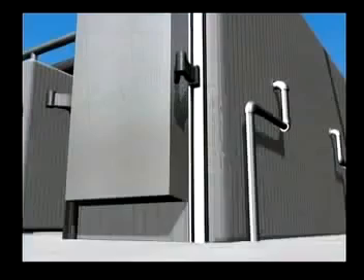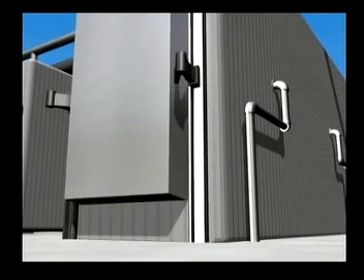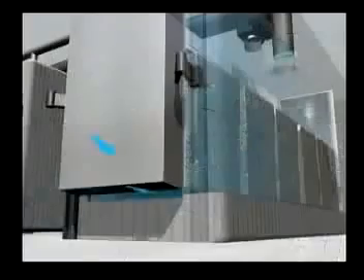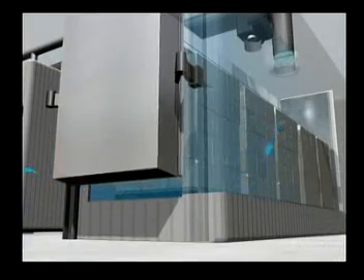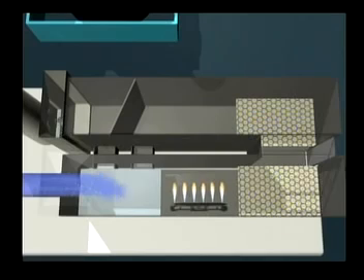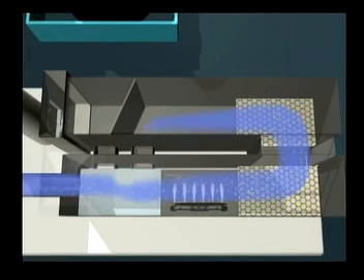before workers can enter. The front door is raised a few inches, which automatically opens a vent at the rear of the chamber. Air is drawn through the chamber to another pollution control device called a catalytic oxidizer. Once the air enters the catalytic oxidizer, it is heated as it passes over open flames. Any remaining traces of ethylene oxide are removed as the air passes over a metal catalyst. After the chamber has been ventilated for several minutes, operators can safely enter to remove the products.